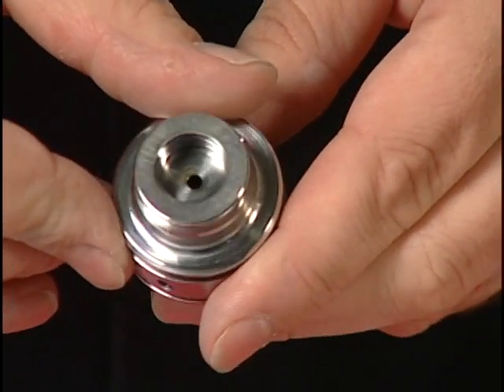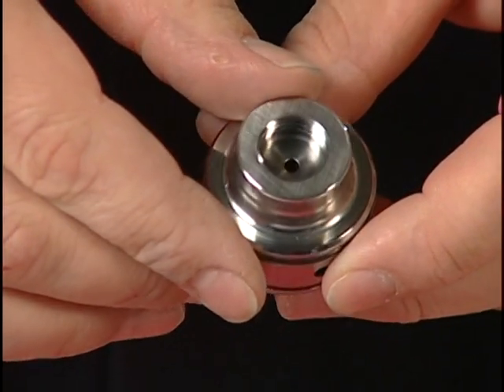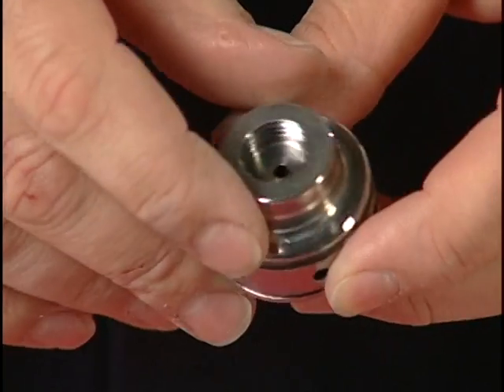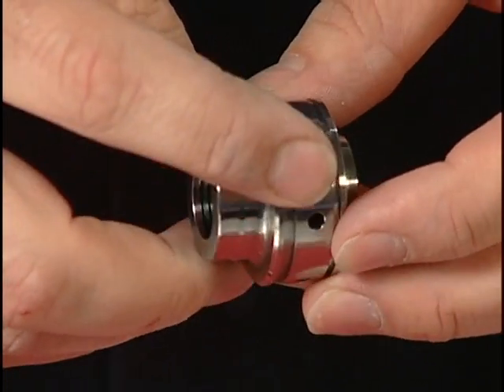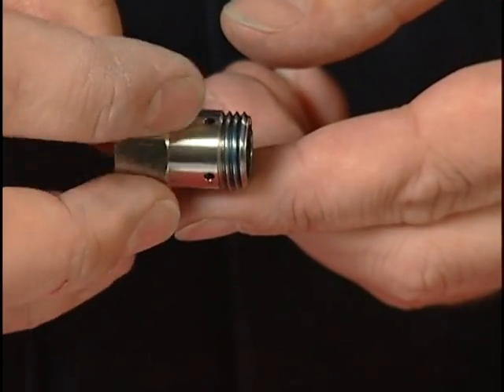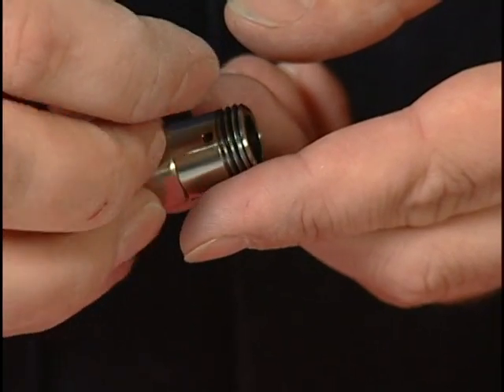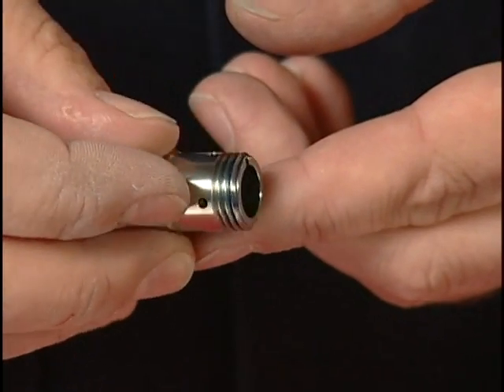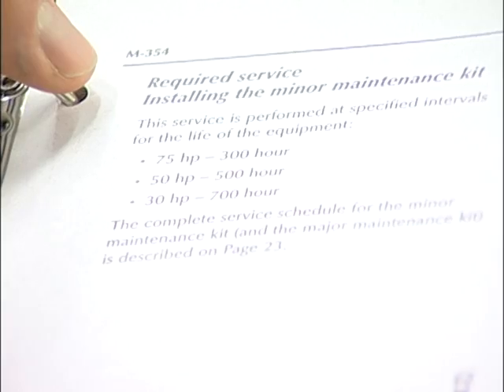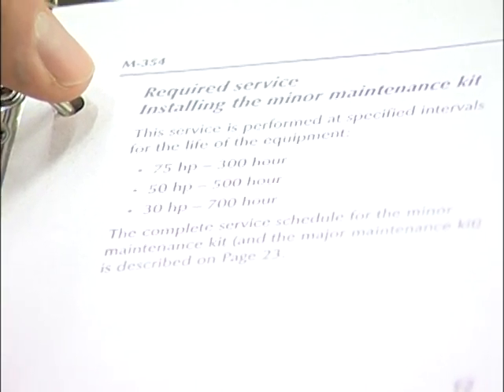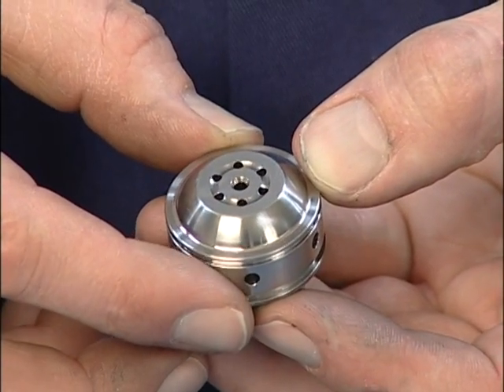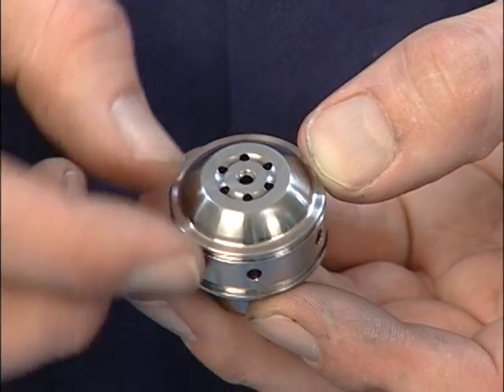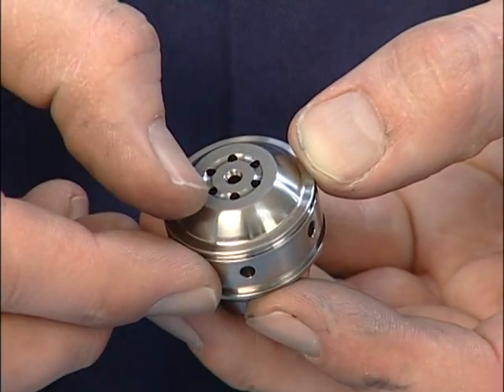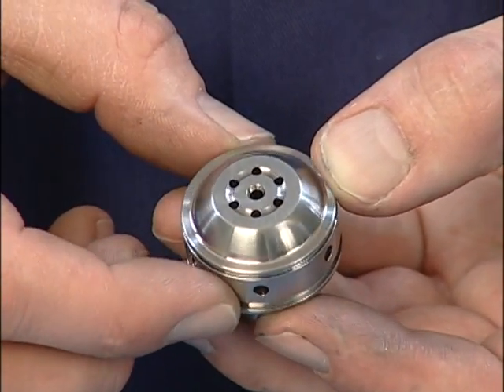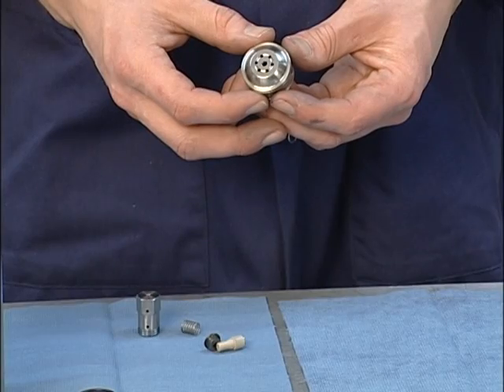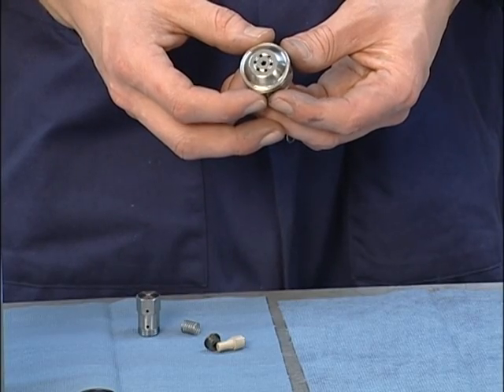Inspect the check valve body for signs of wear, erosion, or pitting. Replace as needed. If this is a scheduled minor maintenance interval, replace the inlet poppet, poppet guide and seat. The major repair service replaces the entire check valve assembly. If deep scratches, erosion tracks, or cracks are found on the inlet face of the check valve body, it should be replaced. If normal wear or minor damage is found on the inlet face of the check valve body, it should be lapped.